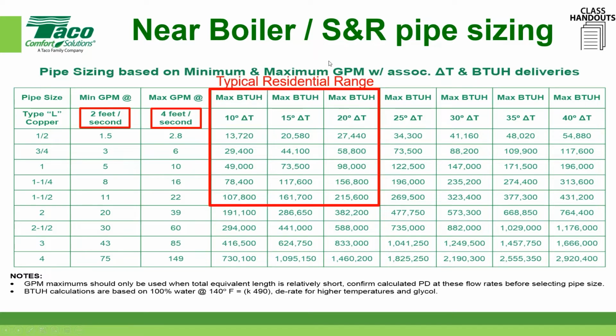The other thing I wanted to show is this delta T thing. Remember, we were just talking about that. So, at a 10-degree delta T, a 15, a 20, etc., what these numbers are is to let you know. Let's give another example. At a 30-degree delta T, I could do a boiler header, the primary portion of a condensing boiler. If I ran 10 gallons a minute through that 1 inch, I could deliver almost 150,000 BTUs at a 30 degree.